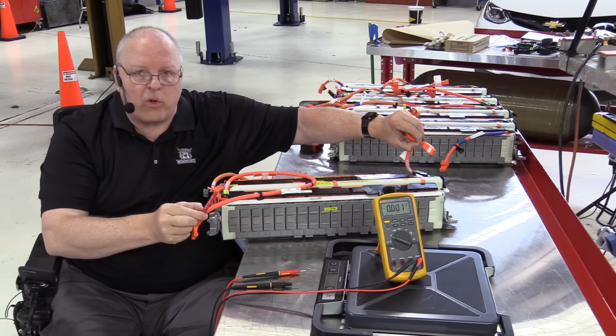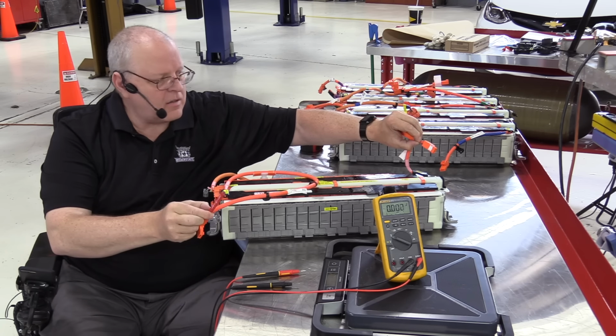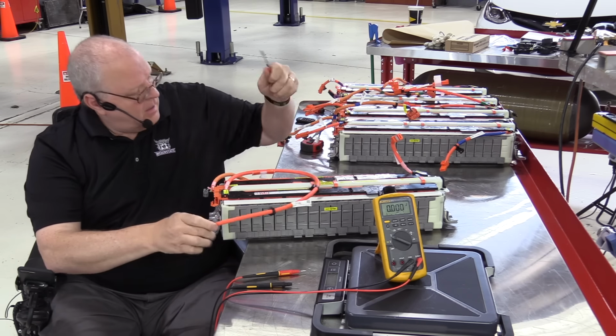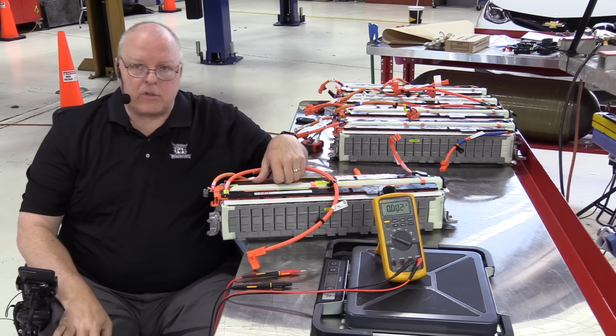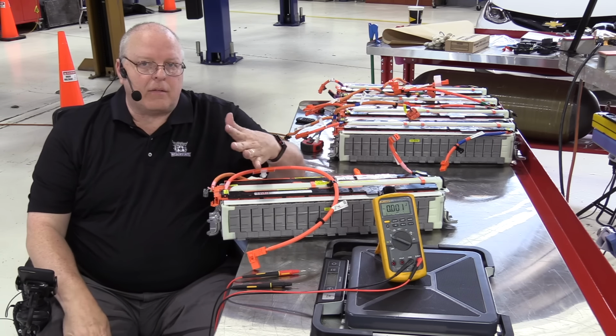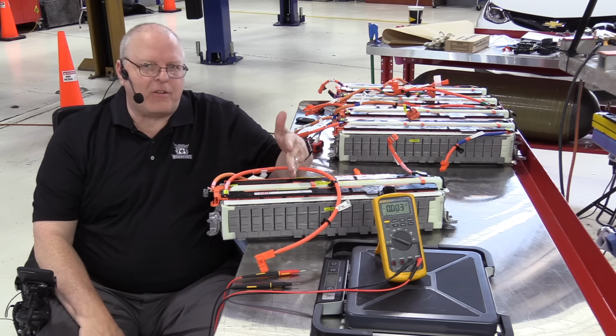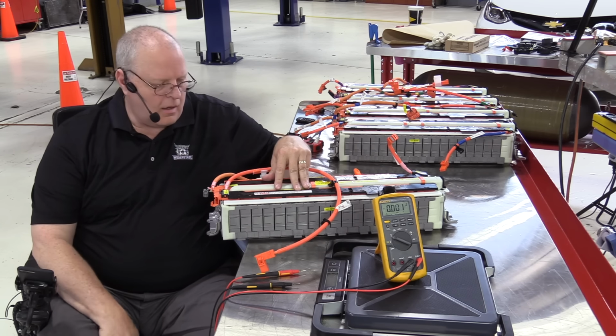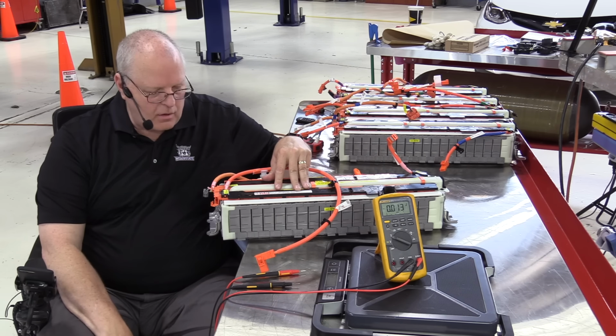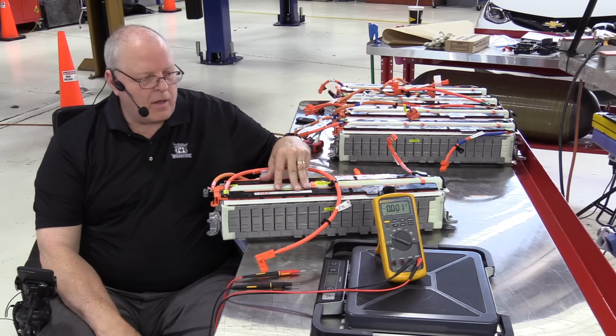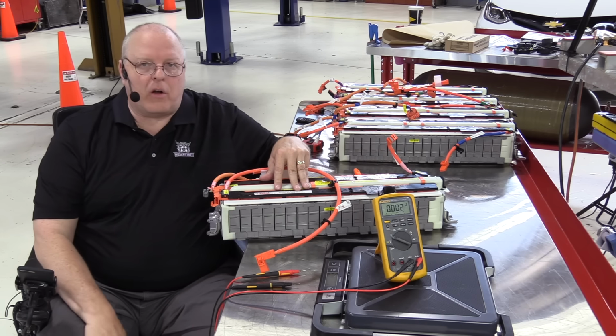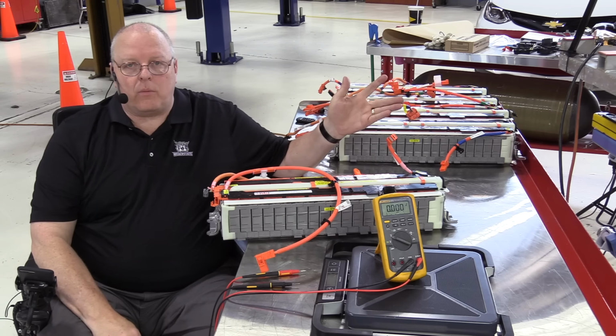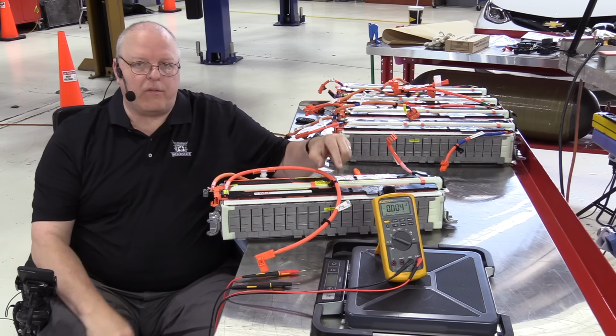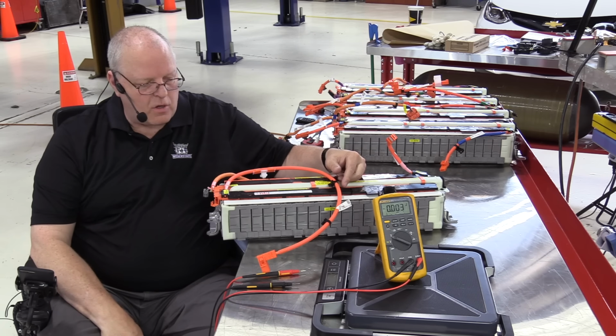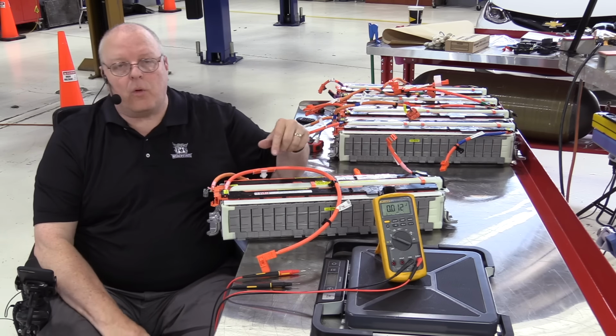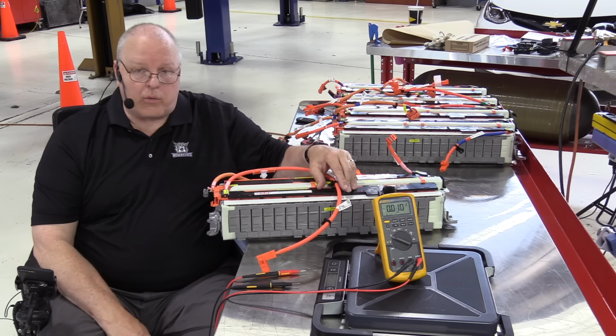Anything less than 100 volts DC and you are okay not to wear PPE. However, many automobile manufacturers in their own service information, to be extra safe, require PPE at 50 volts and above. That's one of the reasons we have a service disconnect lever on almost all of these batteries, to reduce the DC voltage and reduce the chance of getting shocked. Now, once we put all these in series with each other, we'll exceed the 100 volt rating.